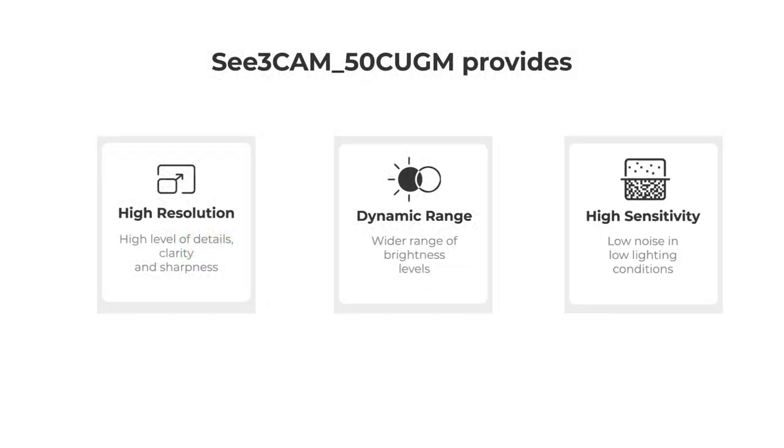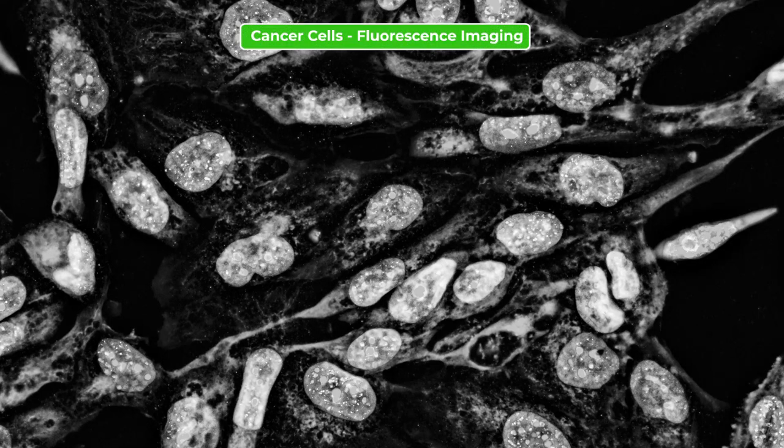The 50CUGM's high sensitivity and low noise makes it a good choice for fluorescence imaging. The monochrome camera does not have a color filter and allows signal detection across wavelengths, thus increasing the overall sensitivity of the camera. The low dark current helps in applications which image at long exposure periods.